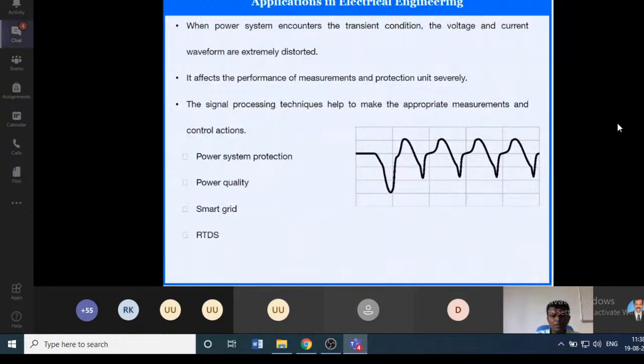So the objective of the protection system is to isolate the faulty section as soon as possible, right? You should act very quickly so that we can clear the fault within the critical fault angle. We have studied in power systems what we mean by critical angle or time. So there is a criterion: if you clear the fault within the critical angle or time, you can ensure the stability of the system. If a fault could not be cleared within the time, then it may lead to the whole system going out of synchronization, and that may lead to an outage of the whole system, right?